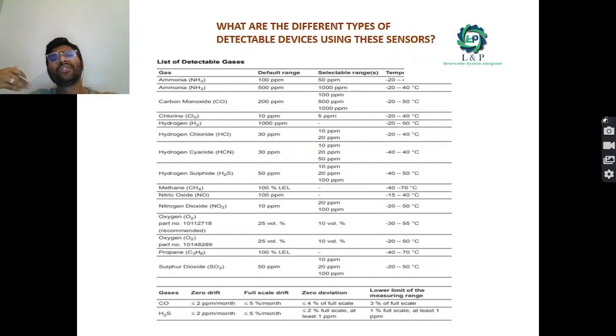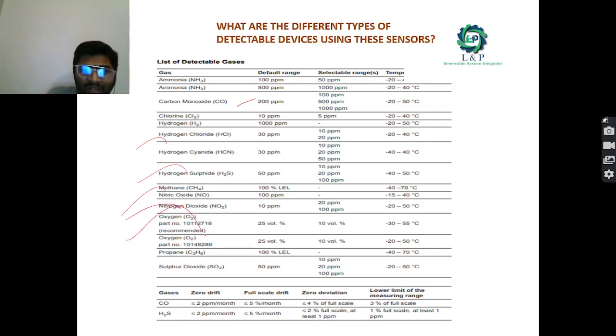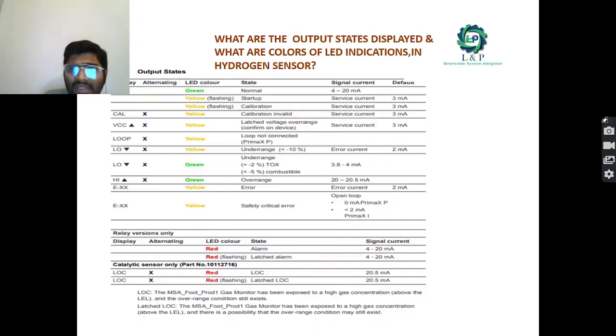And what are the different sorts of gases you can detect using these sensors? We can use these sensors to detect ammonia, carbon monoxide, chlorine, hydrogen chloride, hydrogen sulfide, methane, nitric oxide, nitrogen dioxide, oxygen, propane, sulfur dioxide, carbon monoxide. There are so many different sorts of gases we can detect using this sensor, and the default range will be in ppm.